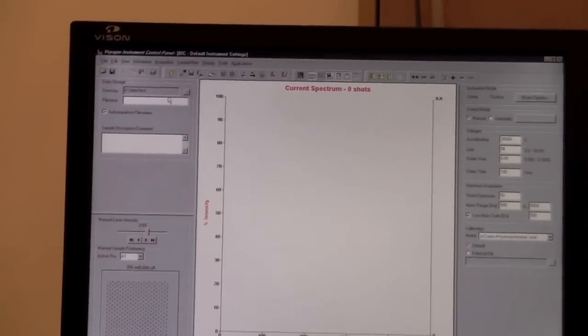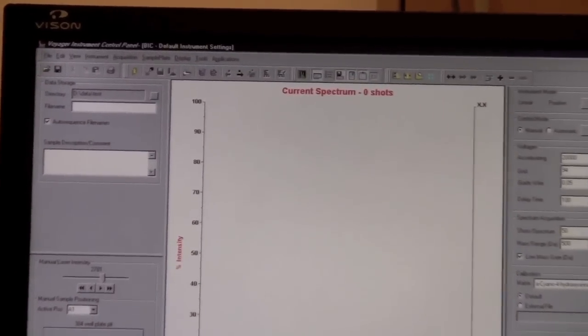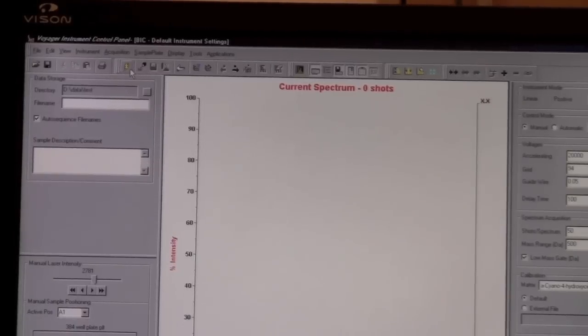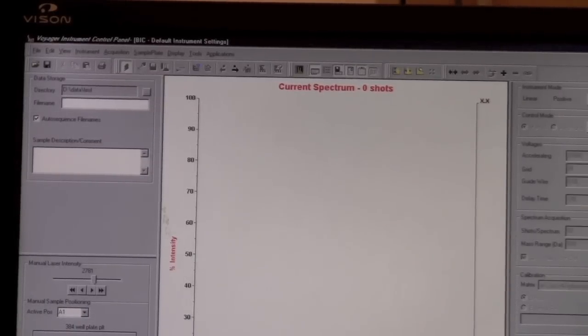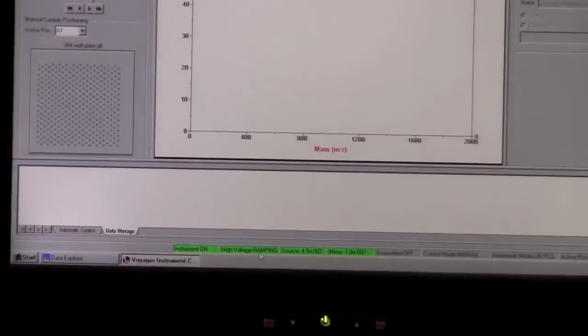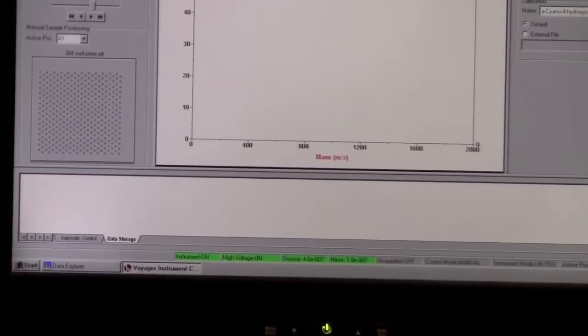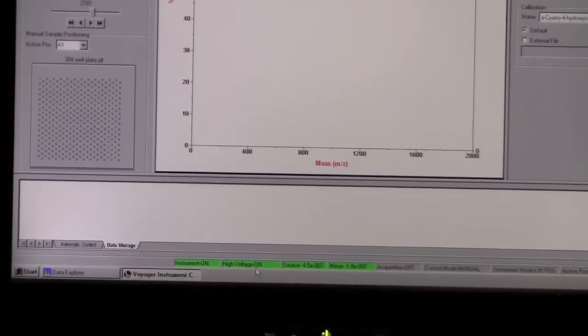The first thing you can do is turn on the high voltage. This is necessary for it to operate. So we'll click on the lightning bolt icon here and it will say high voltage ramping. And then it should ramp the high voltage up to the proper value. So high voltage on. That's good.